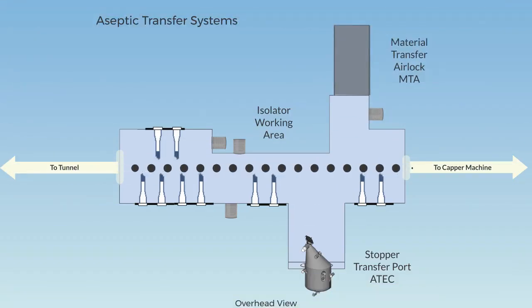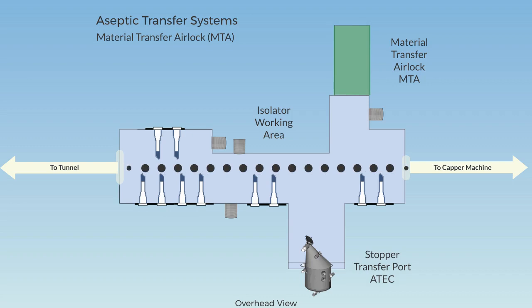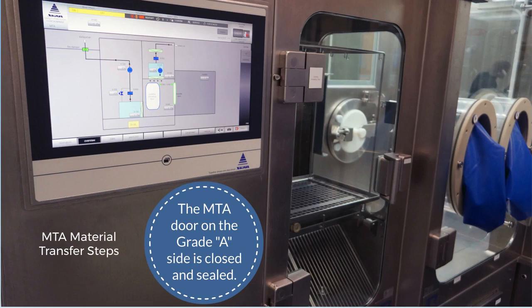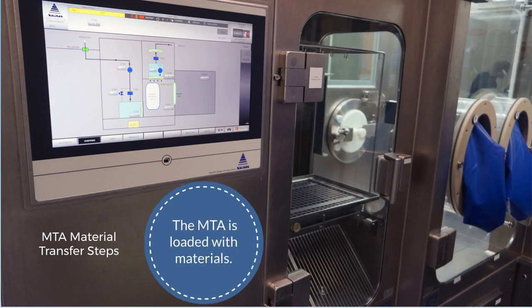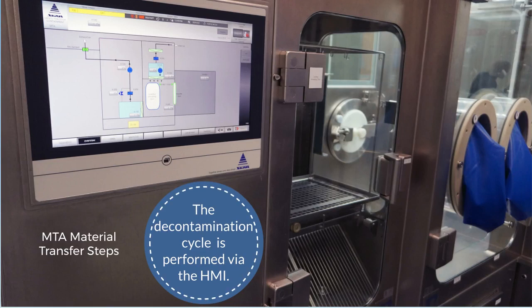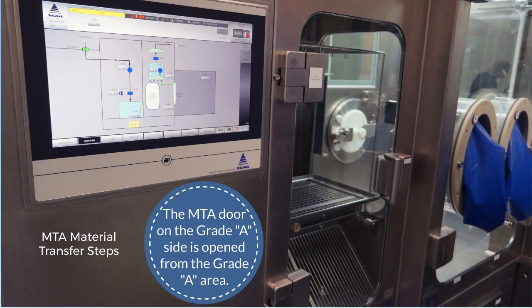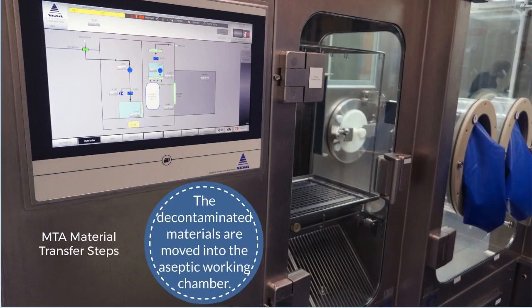The final way to safely move materials into the aseptic working chamber is via a material transfer airlock, or MTA, with an integrated decontamination system. The material transfer airlock door is closed and sealed on the Grade A side and is opened on the Grade C side. The MTA is loaded with materials. The decontamination cycle using vaporized hydrogen peroxide is performed via the HMI. Following cycle completion, the MTA door on the Grade A side is opened by operators working via glove ports within the Grade A area, and the decontaminated materials are moved directly into the aseptic working chamber.